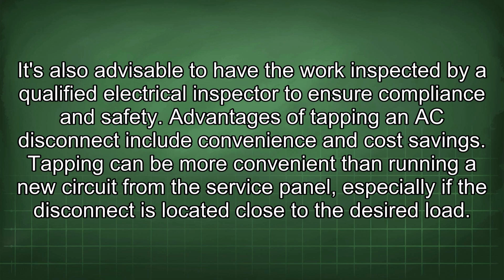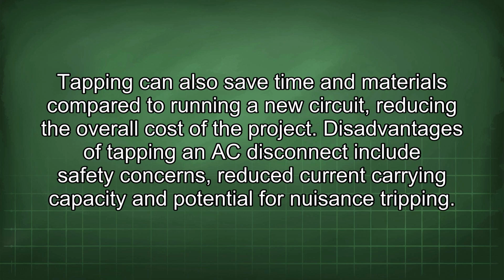Advantages of tapping an AC disconnect include convenience and cost savings. Tapping can be more convenient than running a new circuit from the service panel, especially if the disconnect is located close to the desired load. Tapping can also save time and materials compared to running a new circuit, reducing the overall cost of the project.